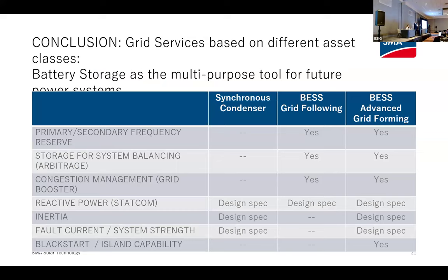Drawing close to the end of my slides, I want to contrast these advanced grid forming capabilities to the typical grid asset that we'd see trying to solve these stability problems on the network, which is a syncon. Syncons are usually designed for specific quantities of reactive power, inertia, and fault current — and that's all that they do. A battery storage plant, in contrast, can provide frequency control, arbitrage, and if you've heard of a grid booster, this is another use case for battery storage for transmission deferral. These are all things that can be monetized by the developer, in addition to those stability services. So we're stacking revenue streams in order to improve a project's economics.